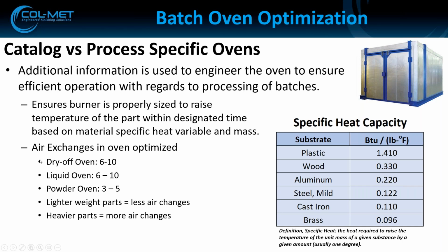We can also design the oven for the number of air changes. Different types of ovens and coatings have different guidelines. A dry-off oven is designed for 6 to 10 air changes. A curing oven for liquid coatings, with more volatiles and air movement needed, is also in that 6 to 10 range. A powder oven needs less air movement so it doesn't disturb or blow the powder off the parts, so we design those for around 3 to 5 air changes.